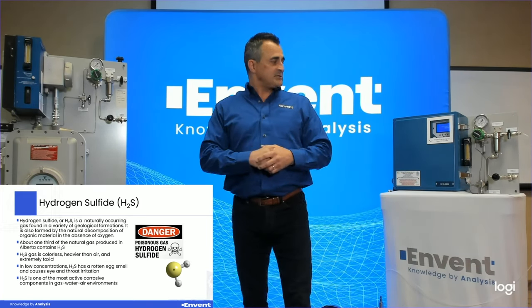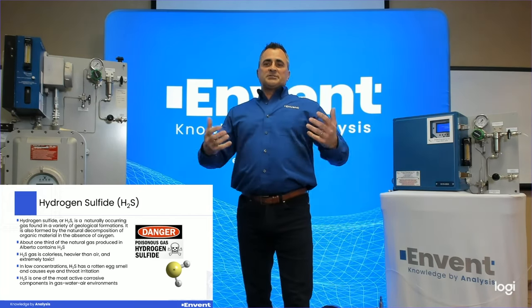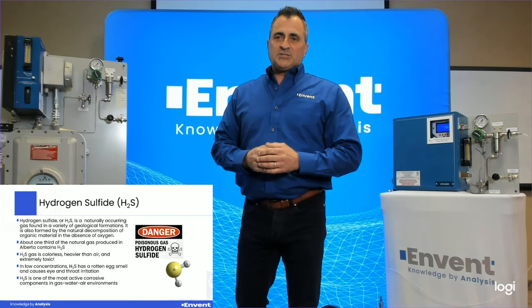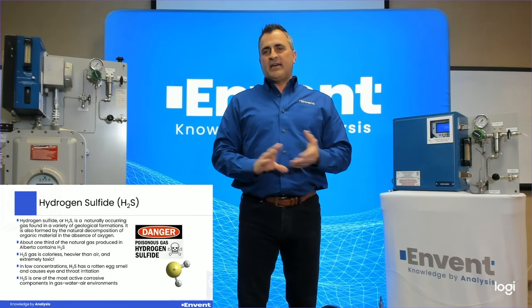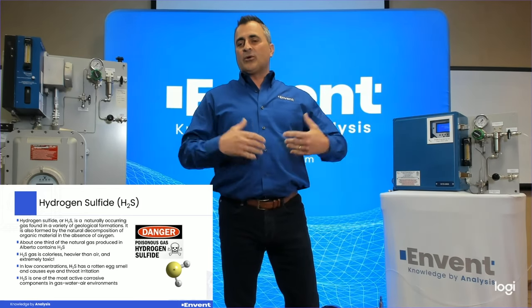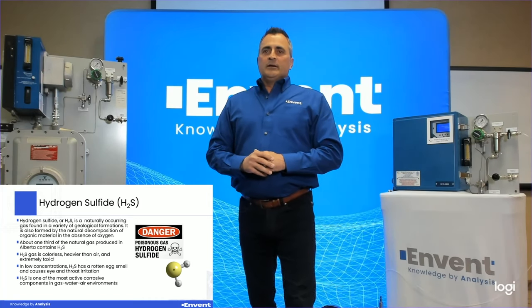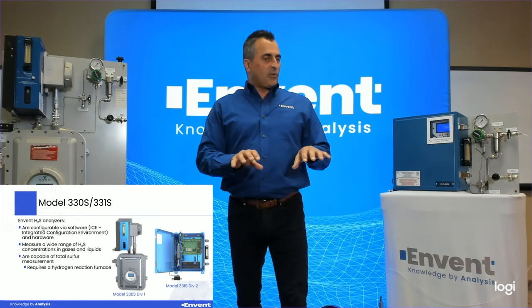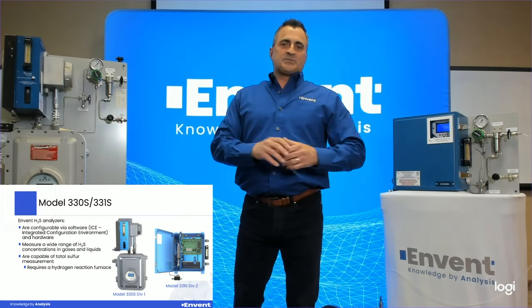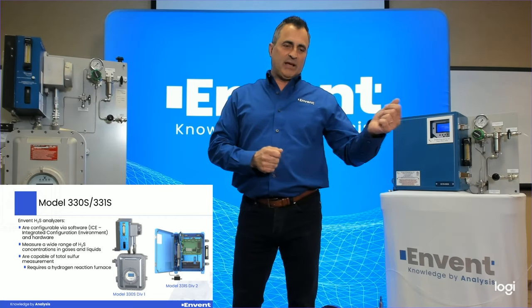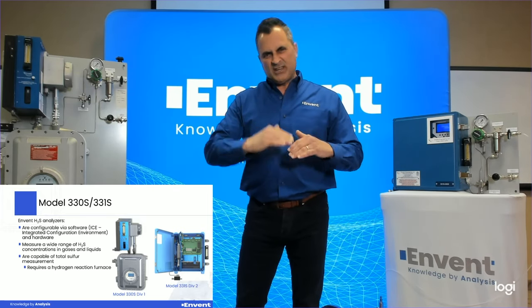Before I get into the nuts and bolts of these devices — which is mostly about service — I need to introduce you to hydrogen sulfide for those who may not be familiar with it. H2S is in about one-third of all natural gas produced in Alberta. It is colorless, heavier than air, and extremely toxic, so we need to monitor for it. These analyzers are configurable with software called ICE, Integrated Configuration Environment — a software package you can plug into any Envent device, with the same look and menu systems.